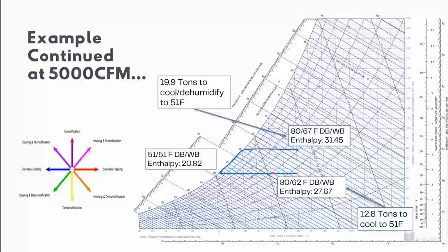And you just cool the entire way to your final target condition without condensing any moisture on a coil. And as a net result of that, 20 tons to cool and dehumidify drops to about 12.5 tons, 12.8 tons to cool to that same target condition.